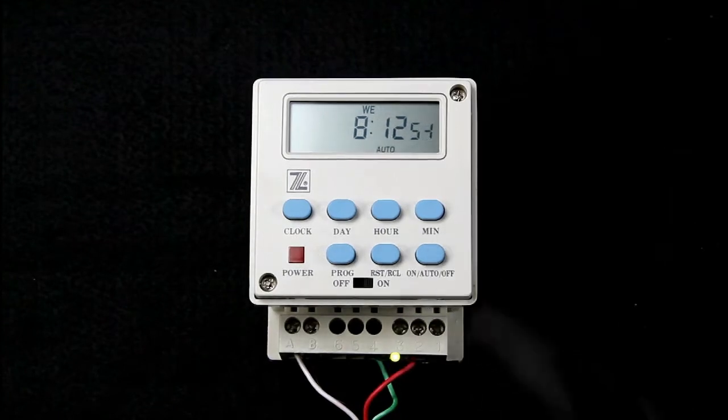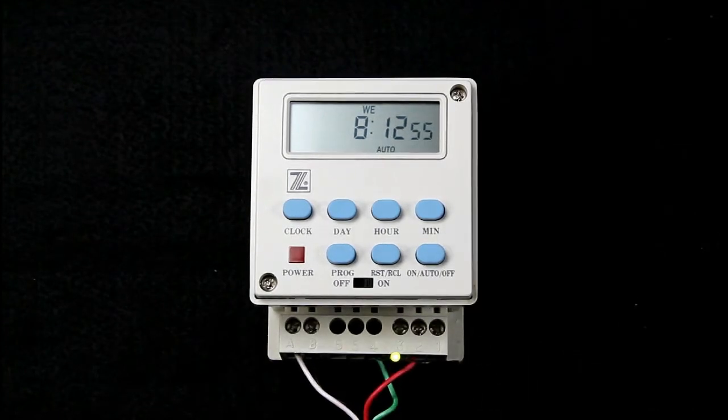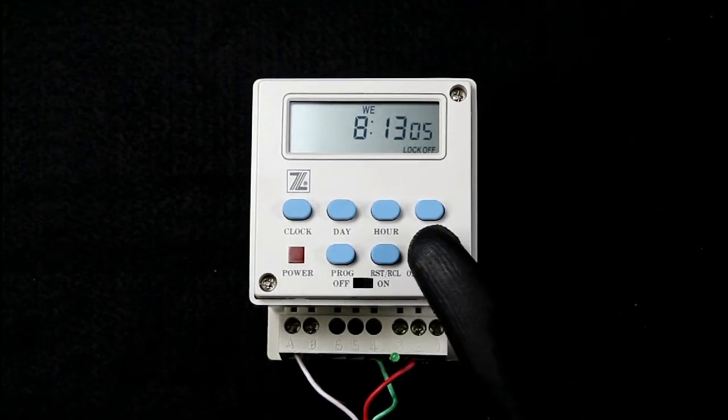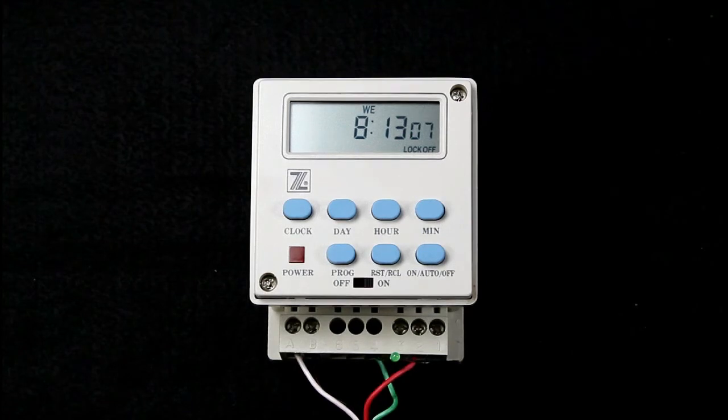Press the on, auto, off button again to show auto. Now the relay will turn off on the next programmed cycle. If you press the on, auto, off button again to lock off, this will turn the relay off and it will remain off indefinitely.